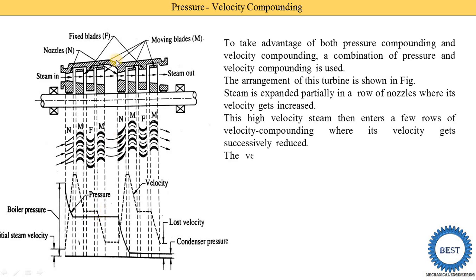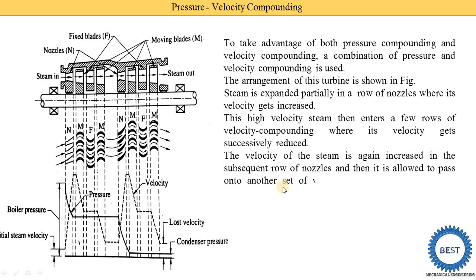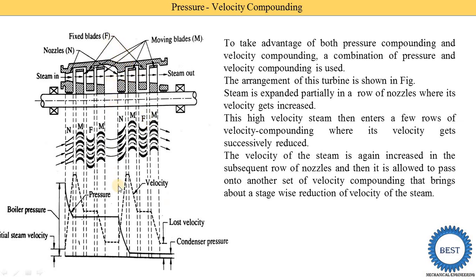Then after, the steam again enters this nozzle. The velocity of the steam is again increased in the subsequent row of nozzles. Here you see the second nozzle: in the second nozzle the velocity increases and the pressure is reduced from partial pressure to condenser pressure. Then it is allowed to pass onto another set of velocity compounding. This again is velocity compounding — we connect the two velocity compoundings in series to achieve the pressure-velocity compounding.